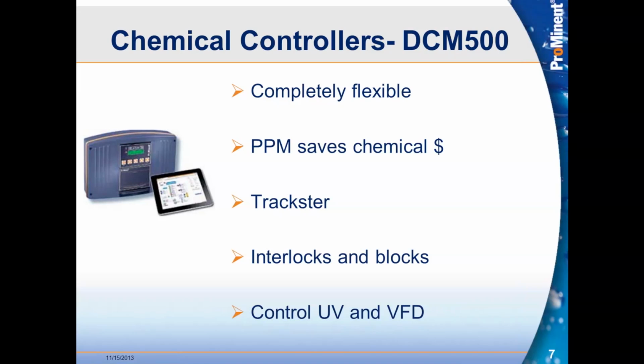The amazing thing about the DCM 5 series to me is the incredible flexibility that it has. What that means is that if you have an architect, a designer, or an end user that wants to do something special, something unique, something that nobody's ever done before, as long as they can give us a sensor for that thing that they want to watch, we can take that signal in, name that signal what it truly is, and then utilize that to make other events occur, controlled by the controller. We can send out alarms based on that event.